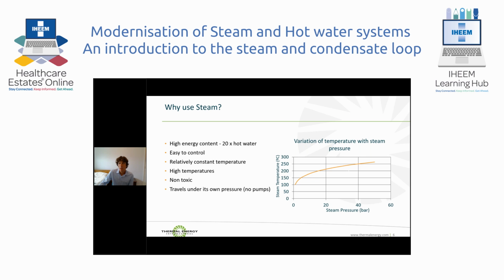We have relatively high temperatures. It's non-toxic. In fact, we can use steam directly in food products, and we often also use it for humidification purposes, directly injecting it into HVAC systems to humidify the air. Steam also travels under its own pressure. There's no requirement for pumps. As long as you maintain the pressure, it will also achieve a relatively constant temperature. So unlike hot water systems, which gradually get cooler as they move around the circuit, if you maintain the pressure of a steam system, the temperature remains constant.